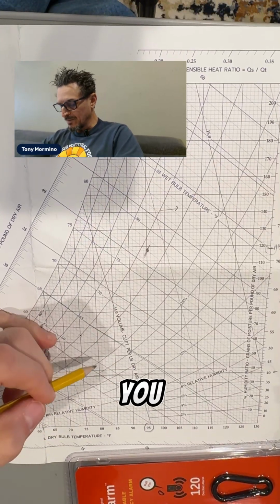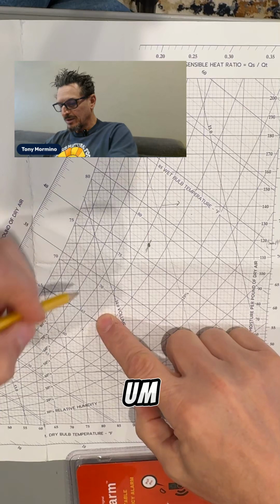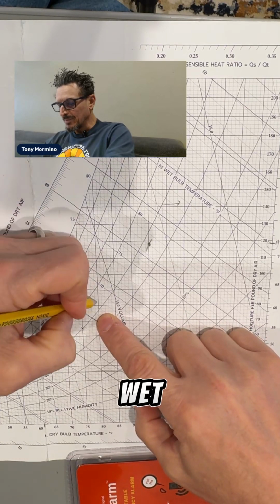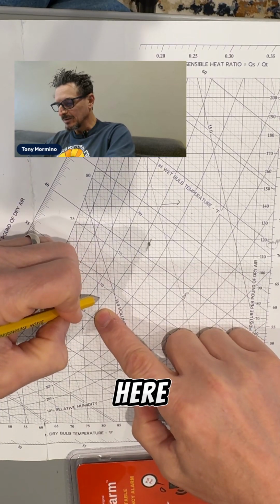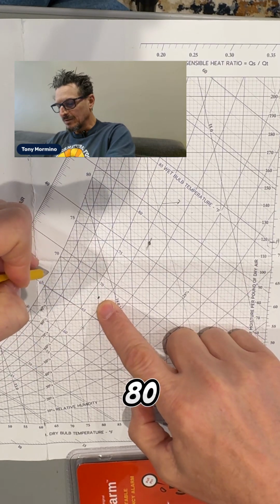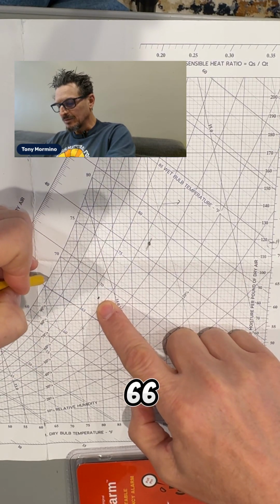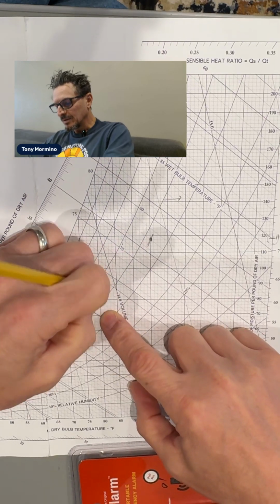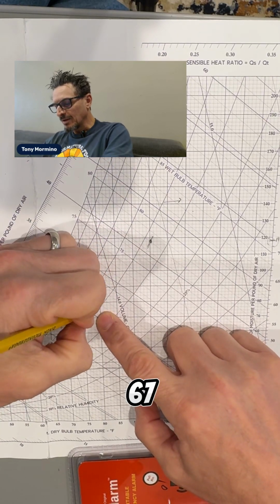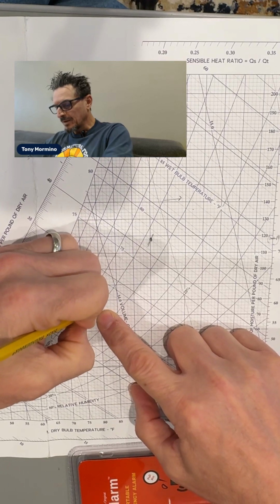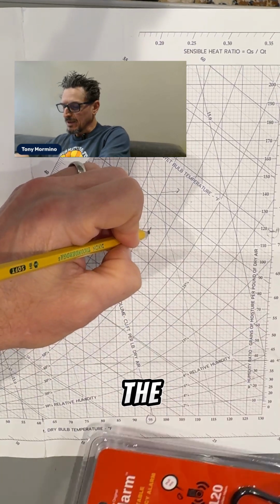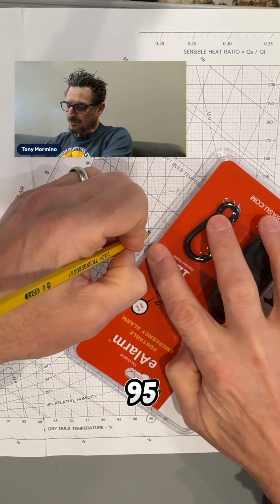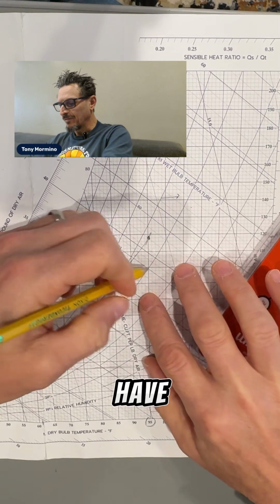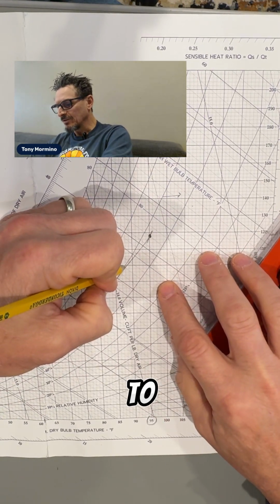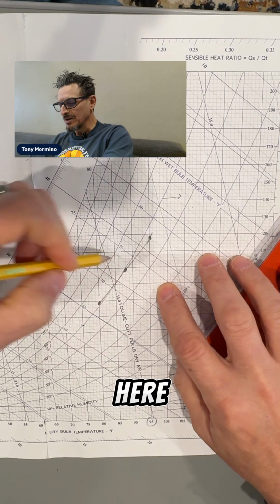So a typical system, you might have 80-degree dry bulb, 67 wet bulb, which falls somewhere around here. 80, 65, 66, 67. Oops, I drew that wrong. Try that again. 67 here. You might mix that with the outdoor air of 95, 78. And let's say you have 50% outdoor air, because that's easy to show here. You would be in this range here.